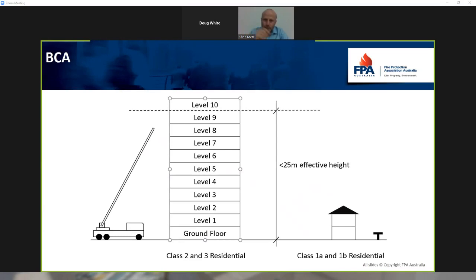And the trigger point, that 25-metre effective height there, which is usually around about 8 levels above ground, is triggered because of the fire brigade appliances with the ladders. That is the max, that's the extent of their reach. So beyond that is where we start to require a great deal more fire protection. So in that region, you know, below 25 metres or 8 floors, there are some relaxations to be had, and that's the space that we're playing in.